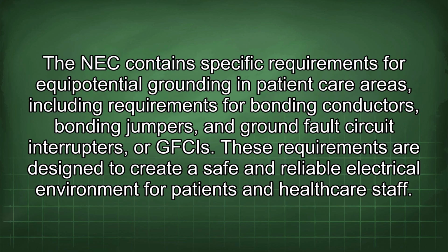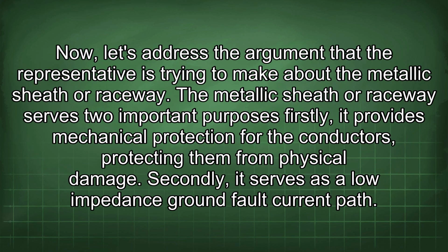The NEC contains specific requirements for equipotential grounding in patient care areas, including requirements for bonding conductors, bonding jumpers, and ground fault circuit interrupters, or GFCIs. These requirements are designed to create a safe and reliable electrical environment for patients and healthcare staff. Now, let's address the argument that the representative is trying to make about the metallic sheath or raceway. The metallic sheath or raceway serves two important purposes. Firstly, it provides mechanical protection for the conductors, protecting them from physical damage.